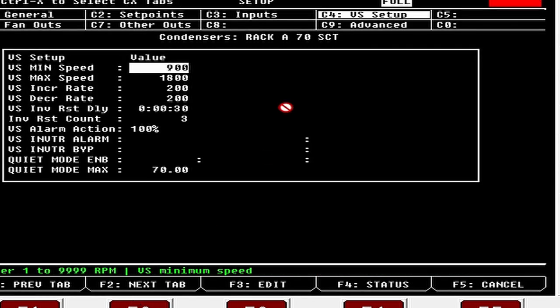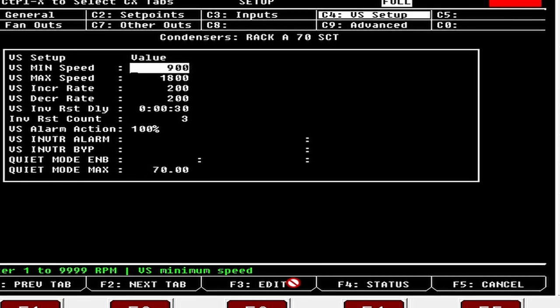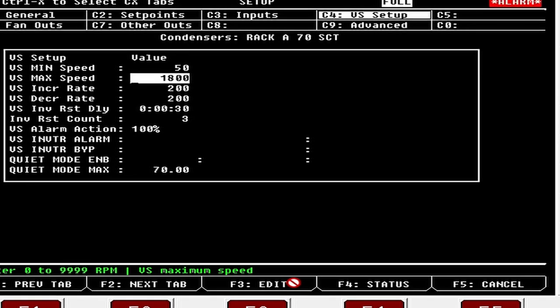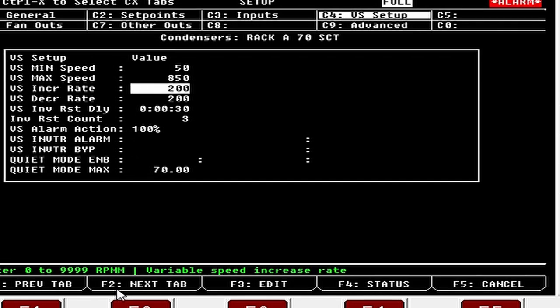The next tab is your Variable Speed setup. This is how it comes from the factory. I generally go about 5% on the motors for minimum speed; some motors require 10% minimum. For an 840 RPM motor I generally go about 100 RPMs, sometimes you can get down to 50 RPMs. If you're using EBM motors you can get way lower — we'll make this 850 whatever it is. Then we have your Variable Speed Increase and Decrease Rates.